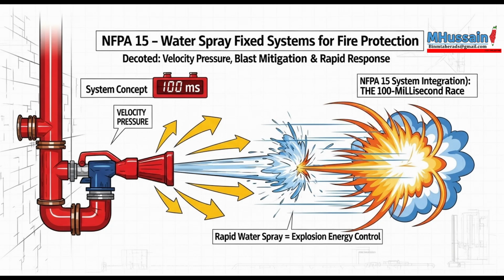No. It's potentially catastrophic. So our mission today is to pull out those critical engineering parameters, the hydraulic details, the compliance hurdles, all the things that make NFPA 15 design just a completely different beast compared to, say, regular sprinkler installation. That's a great way to put it, a different beast entirely. Because for our listeners, you engineers and learners living in this world, NFPA 13, that tells you how to protect an office building, right? Right. Standard stuff. But NFPA 15, this is about protecting a massive transformer or maybe a high-pressure vessel holding volatile materials. It shifts the whole focus.